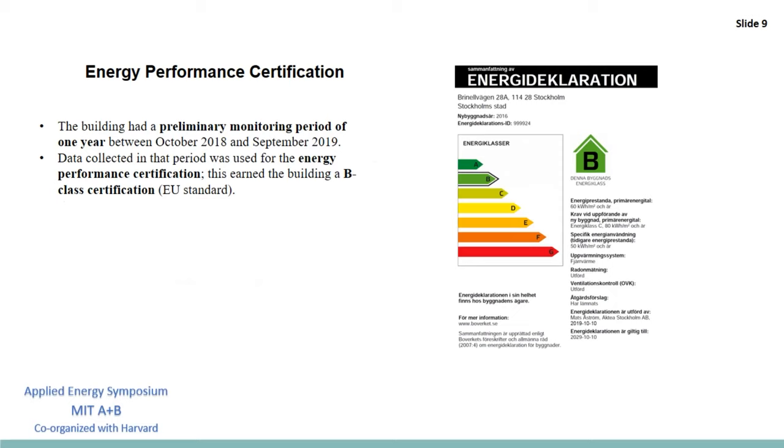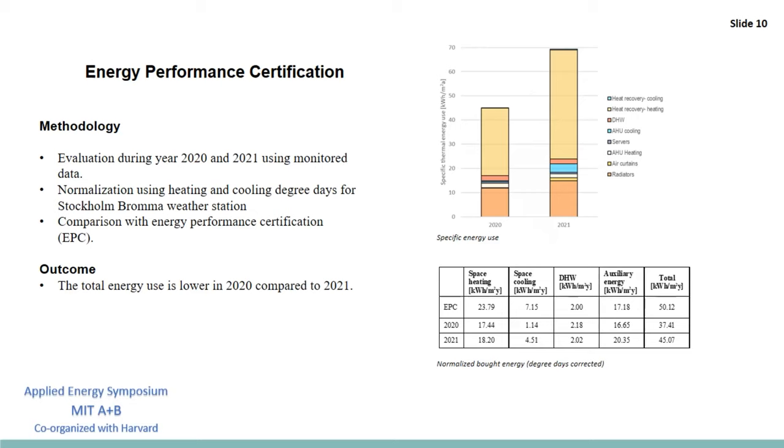Before looking at the monitored energy data we need to say that the building had a preliminary monitoring period of one year between October 2018 and September 2019 and earned a B-class certification according to the EU standard. We then analyzed monitored energy data for 2020 and 2021. Specific energy use is reported in the bar chart. The table below shows normalized energy use for 2020 and 2021 and for the year of certification. Specific energy use is much lower in 2020 as compared to 2021. In both years we can appreciate the importance of heat recovery that covers a very large part of the demand. The normalized energy use in 2020 is significantly lower than 2021 and the one of 2021 is lower than the one of the energy certification year. The normalization was done using the heating and cooling degree days.